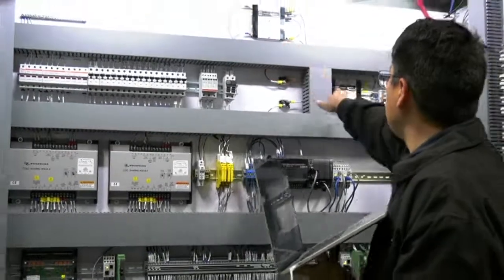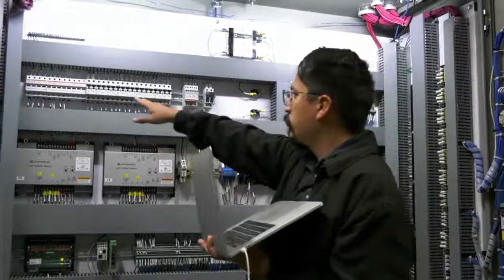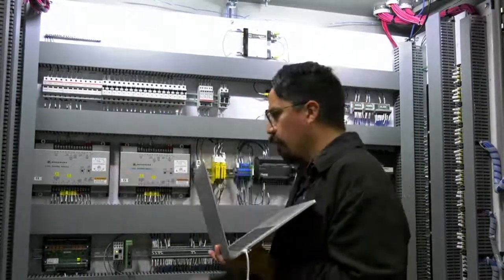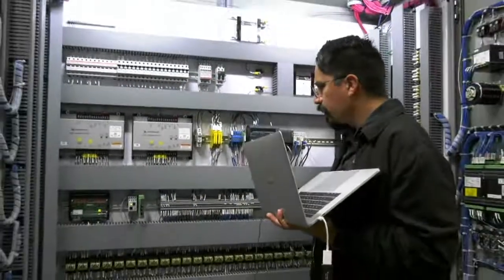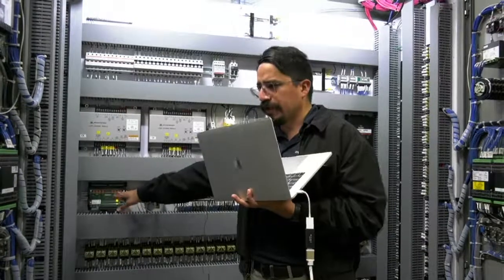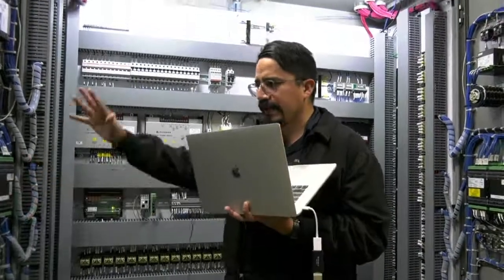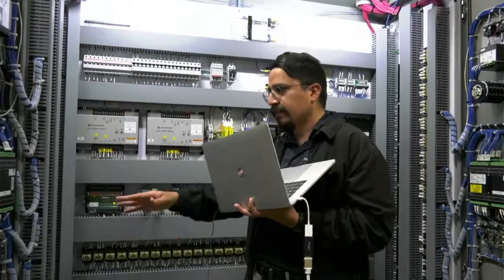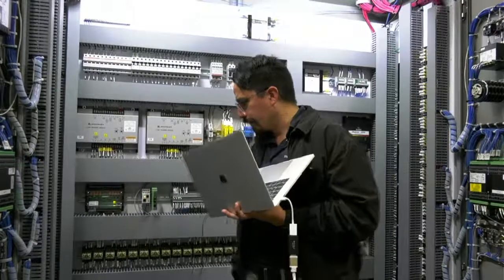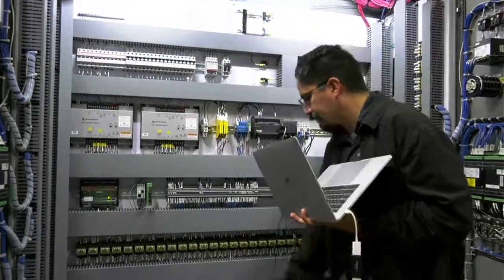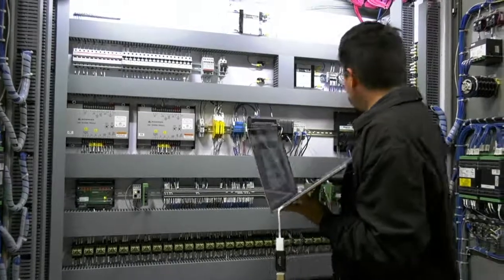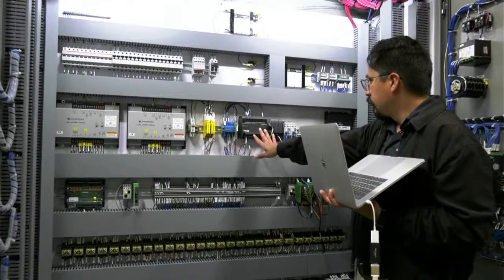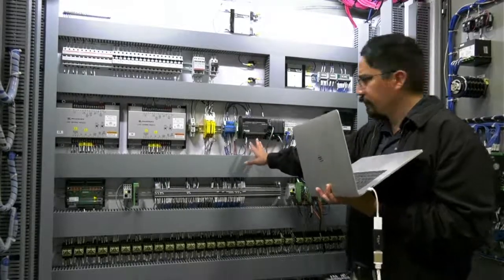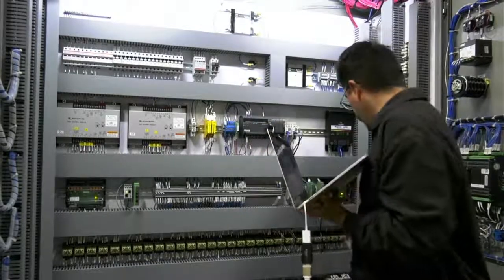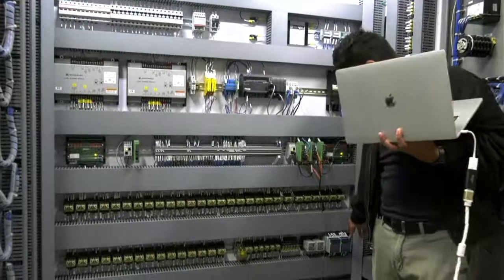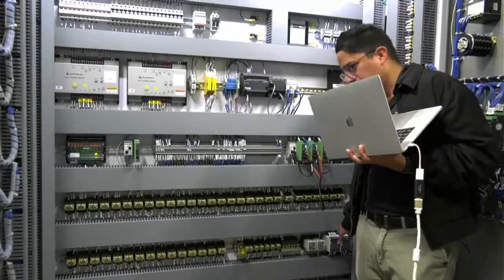On the top we have power supplies, some circuit breakers, protection for all the wiring, and main terminal blocks. These are basically remote IOs for the EasyGens, so they expand the amount of inputs and outputs of this control over here. We have some relays, normal relays, external relays, and some PLC over here, mostly for communications and Modbus. Jesse can talk about this more, and some protections over here. Those are Woodward protections. Those help for manual control.